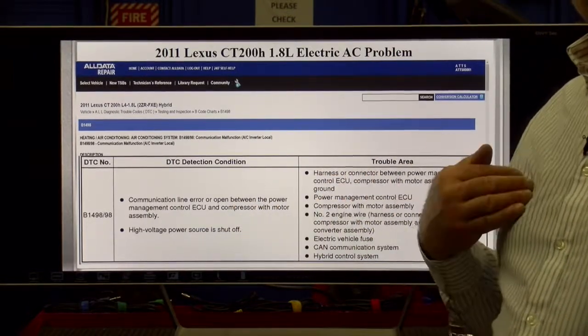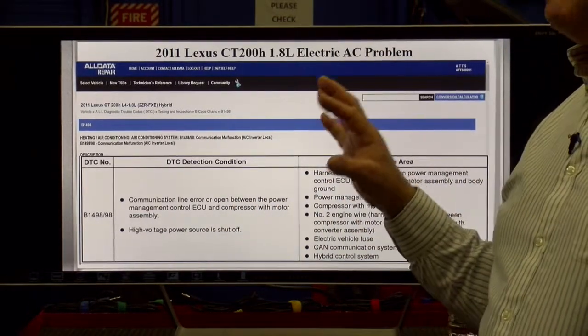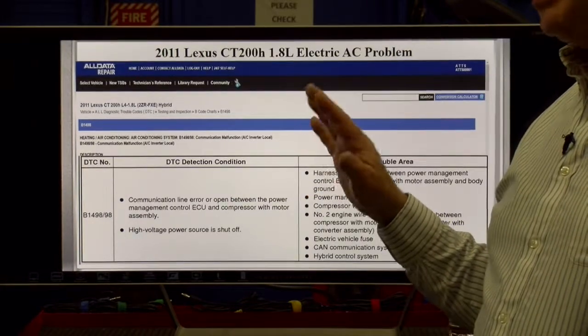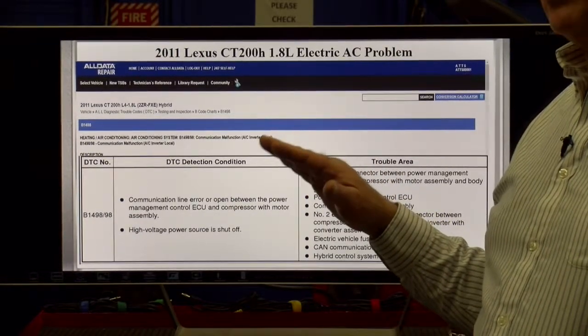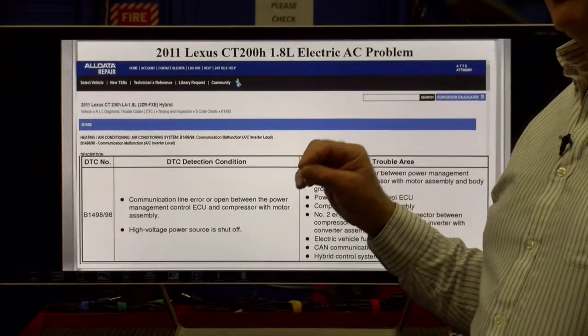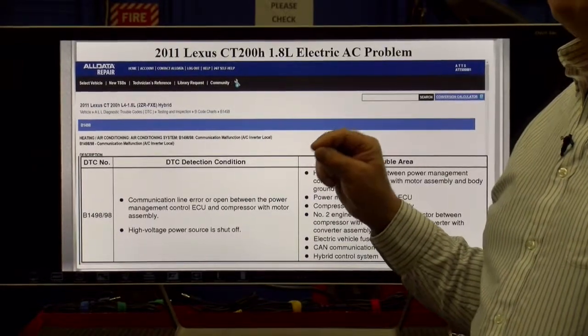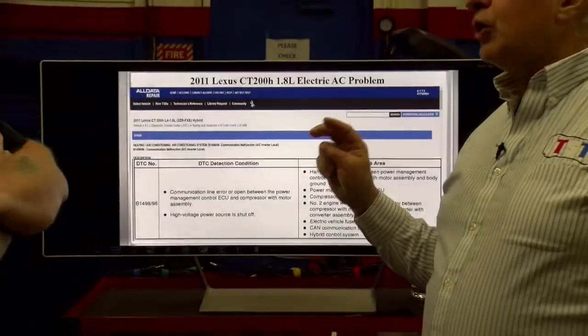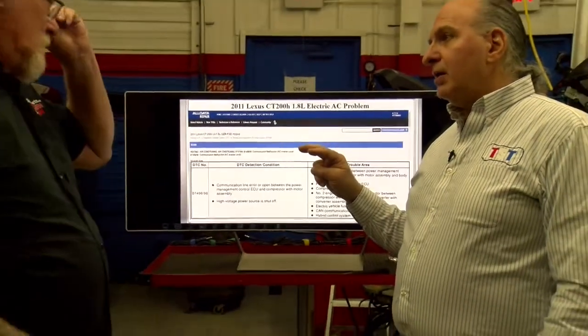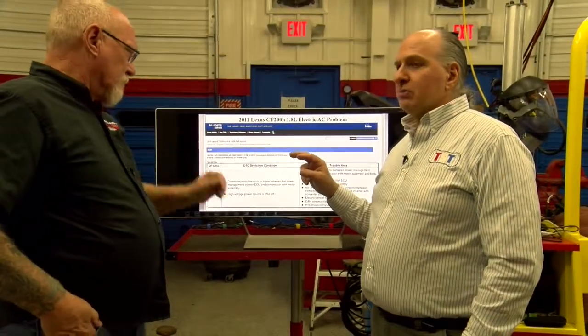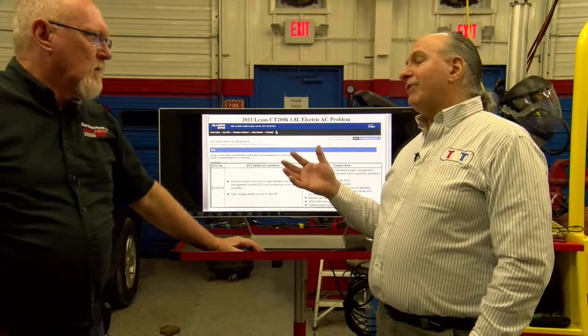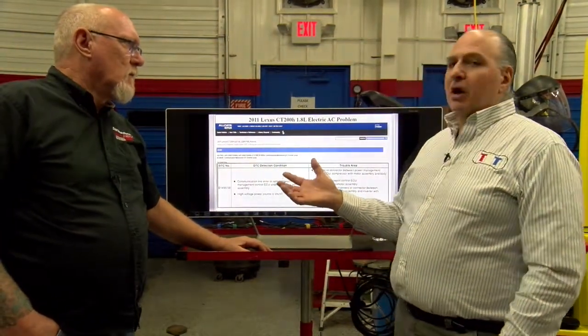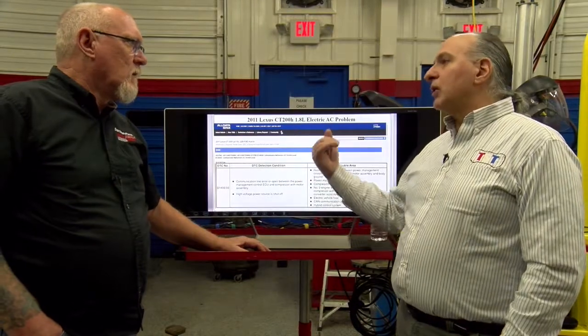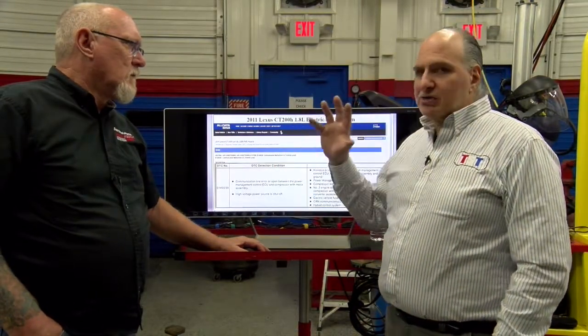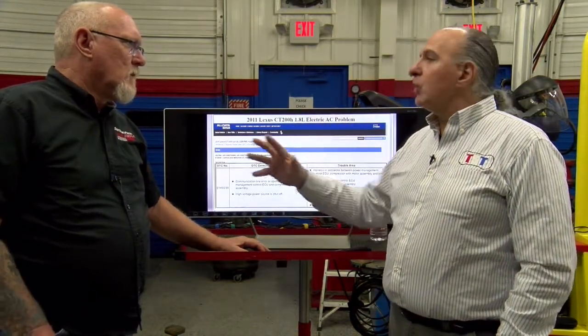So what we would do is shut the main power off, make sure the capacitors are drained down in the inverter, open the inverter up, use our meg ohm meter on that circuit, and read factory information, because it may tell you put 500 volts, put 250 volts. Years ago you'd say whatever power going through, you double the power, but Toyota has specific recommendations.